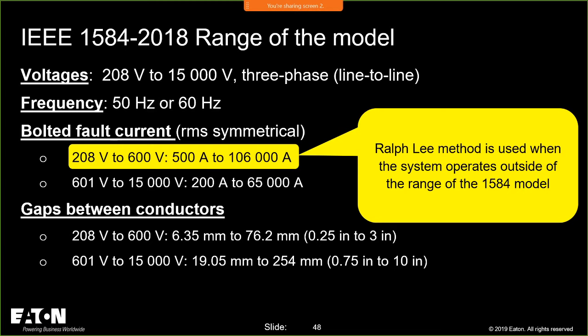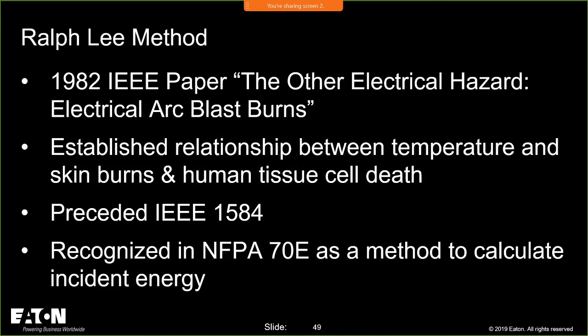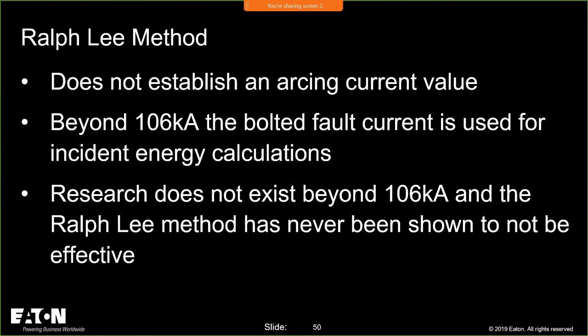It doesn't meet the requirements of the NEC, because the NEC specifically says arcing current, and the only thing I have to calculate arcing current is 1584. That presents the challenge. Now, the Ralph Lee method was a paper that was presented back in 1982. It established a relationship between temperature and this. Remember, 82 precedes IEEE 1584, whose first edition was 2002, and the next edition was 2018. So 1982 is well before IEEE 1584 came on the market, and again, it's recognized in 70E as a method to calculate incident energy. It doesn't establish an arcing current value. So again, it uses the three-phase bolted fault current value.